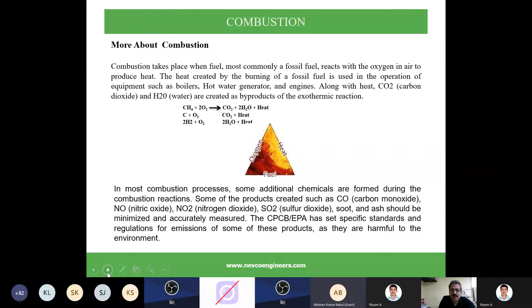The objective of combustion is to retrieve energy from the burning of the fuel in the most efficient way possible. To maximize combustion efficiency, it is necessary to burn all the fuel with the least amount of losses. The more efficiently fuel is burned and energy gathered, the cheaper the combustion process becomes. Complete combustion occurs when 100% of the energy in the fuel is extracted, but practically it is not. It is important to strive for complete combustion to preserve fuel and improve the cost efficiency of the process. There must be enough air in the combustion chamber for complete combustion to occur. Excess air greatly lowers the formation of CO by allowing CO to react with O2.